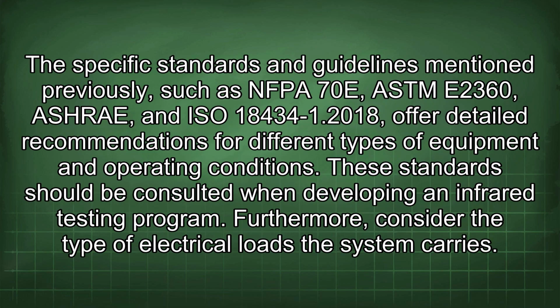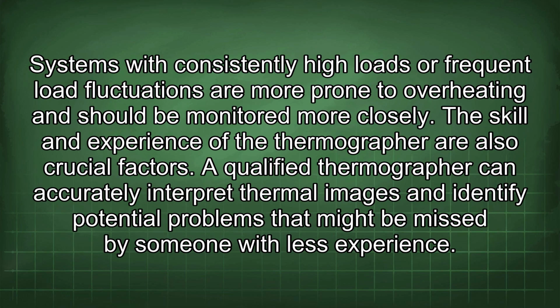The specific standards and guidelines mentioned previously, such as NFPA 70E, ASTM E2360, ASHRAE, and ISO 18434-1:2018, offer detailed recommendations for different types of equipment and operating conditions. These standards should be consulted when developing an infrared testing program. Furthermore, consider the type of electrical loads the system carries. Systems with consistently high loads or frequent load fluctuations are more prone to overheating and should be monitored more closely.